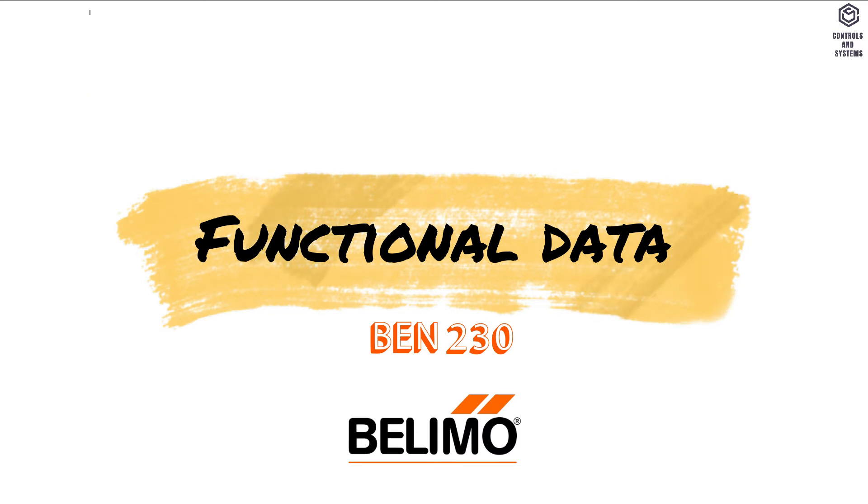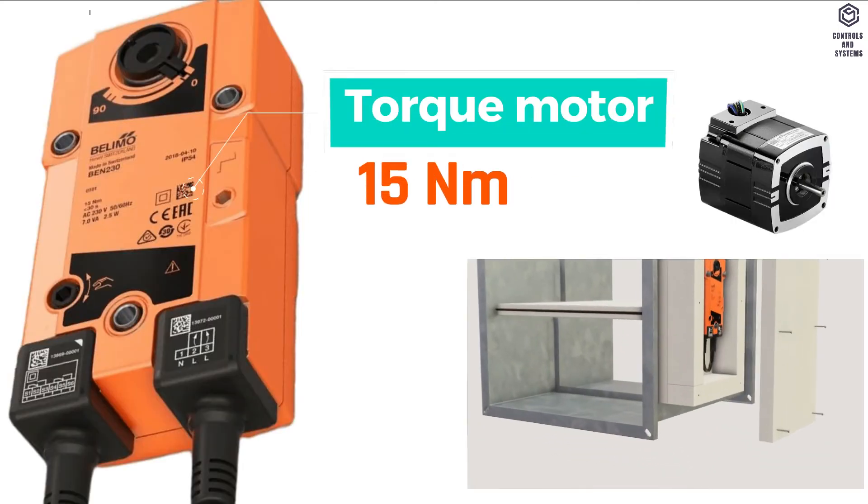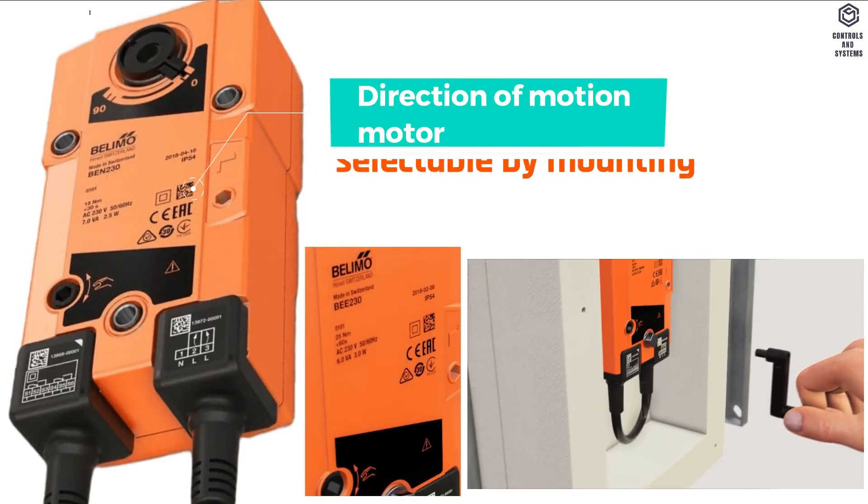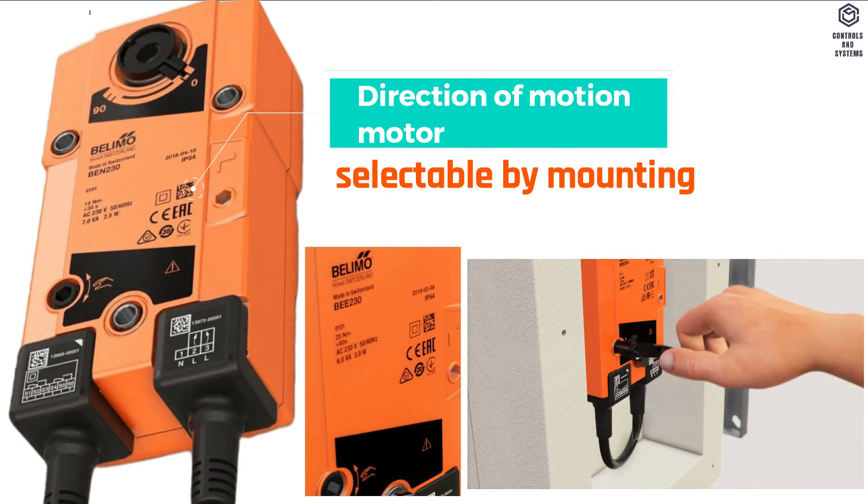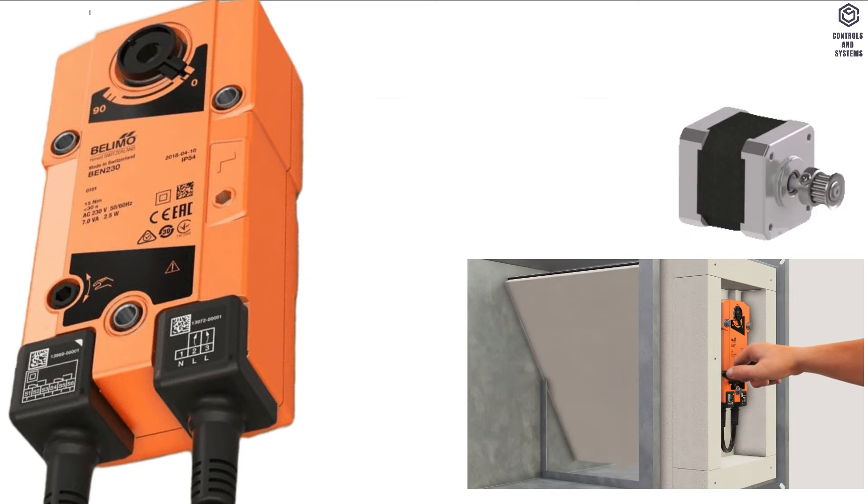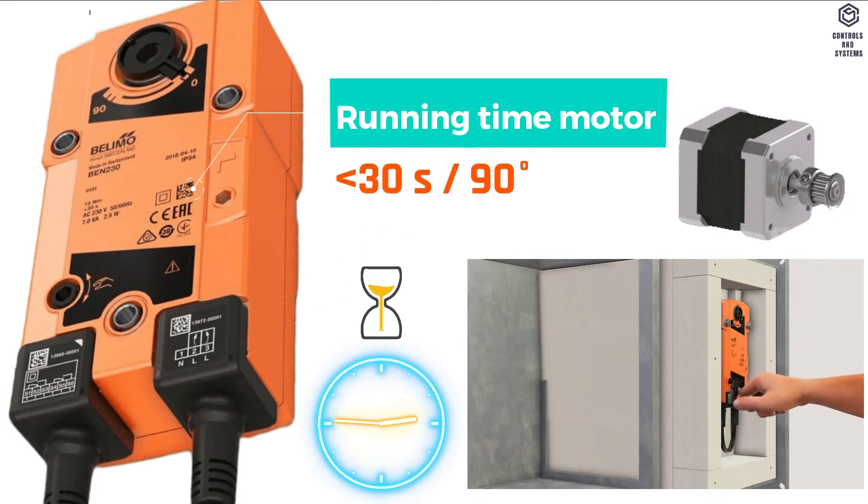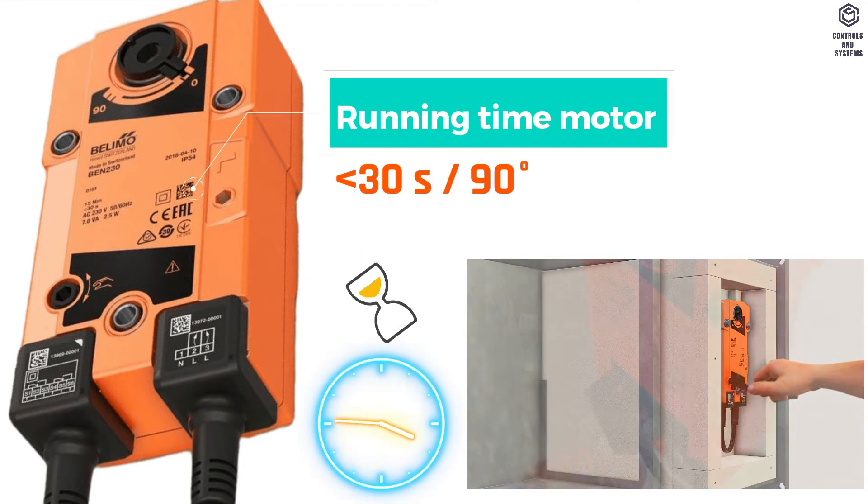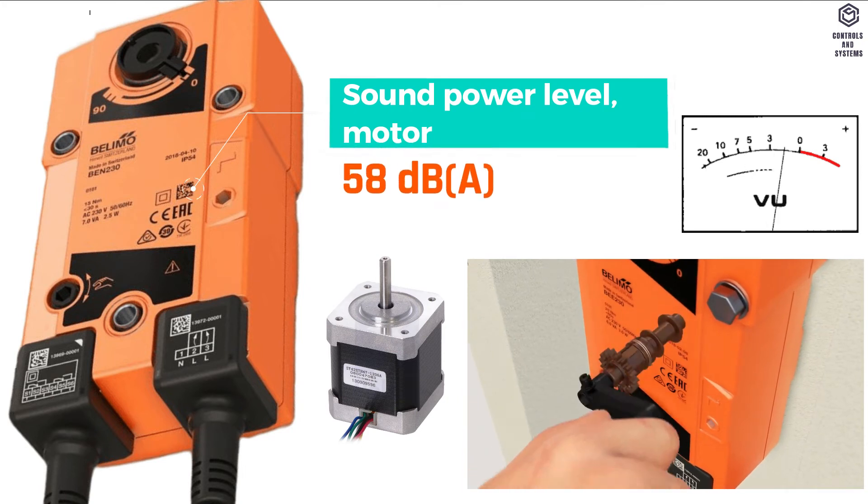Functional data: torque motor is 15 newton meters, direction of motion motor is selectable by mounting, angle of rotation is maximum 95 degree, running time motor is less than 30 seconds at 90 degree. Sound power level of motor is 58 dB.